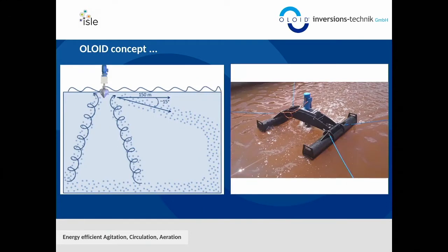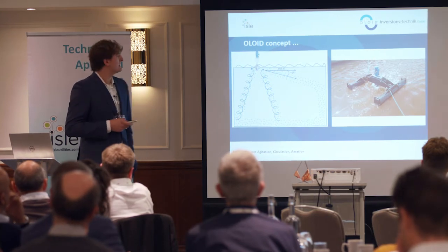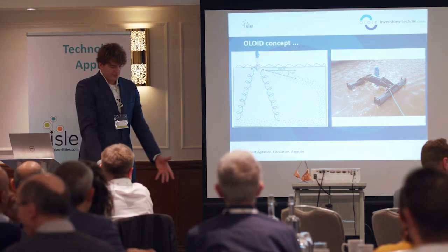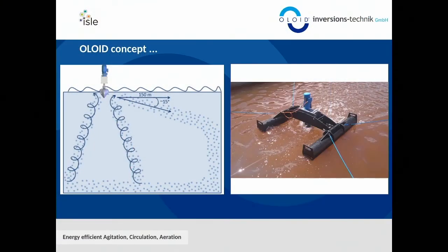To show the concept: in conventional mixing technology, you have a flow from left to right in this picture, with the propeller creating a sucking area and a pushing area. What we do with the Oloid's movement is a 90-degree change in direction. This gives us the ability to bring water up from the bottom of a tank and keep it in movement with low energy. Clients often say the flow is going everywhere because you can see waves across the whole tank, but the waves are generated by us — the main flow is actually in one direction.